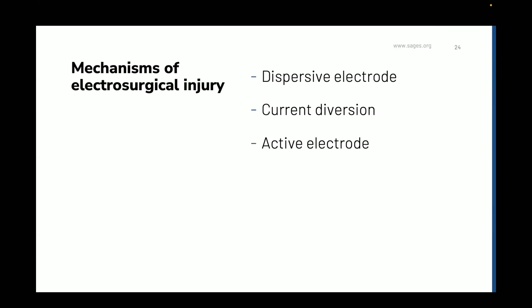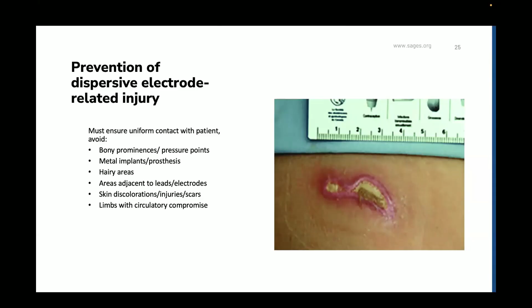To prevent injuries from the dispersive electrode, you have to make sure that it is in uniform contact with the patient, because the whole way it works is that it's spreading the current through a high surface area. If it's partially disrupted, it can lead to potential burns. So we want to avoid placing these on bony prominences, metal implants, or hairy areas where it might not stick properly, or adjacent to things that can conduct current, such as leads or electrodes, any skin discolorations, or limbs with circulatory compromise.